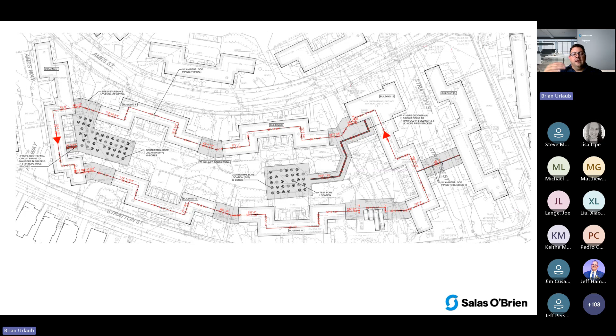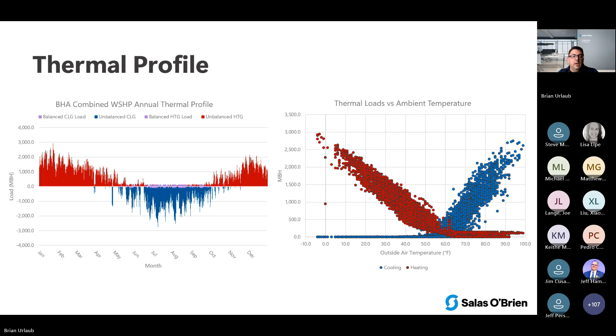So they're doing envelope improvements to reduce the peak to 20 BTUs max. When we went through all those measures and modeled everything at the end, we realized we don't need boilers. But let me show you a little bit of when we were looking at the boilers, and how that impacts whether we want one boiler in one location or two boilers, one at each location, and how that affects things.